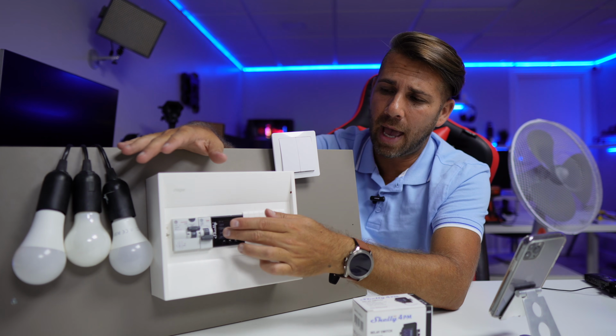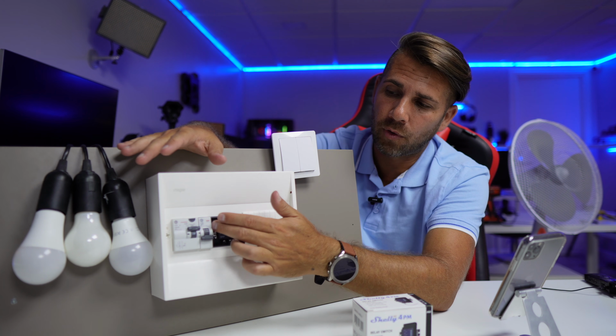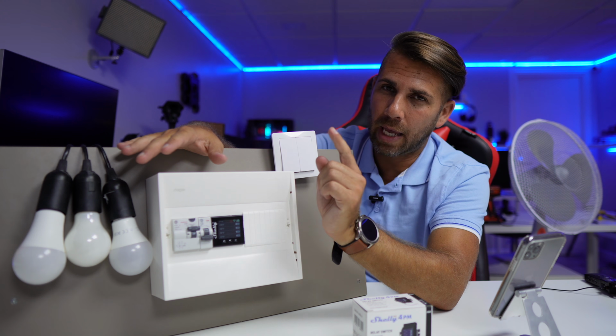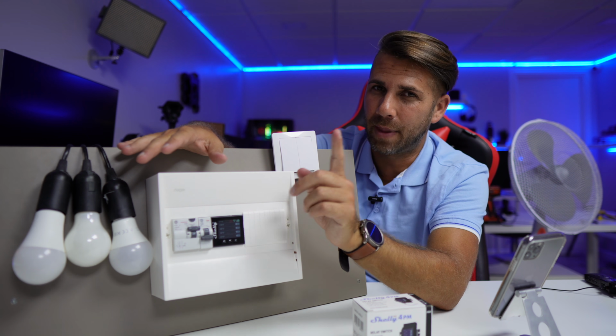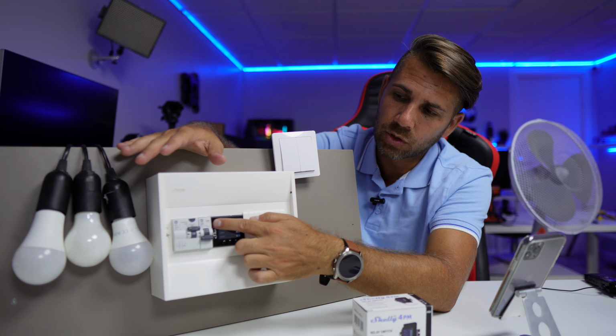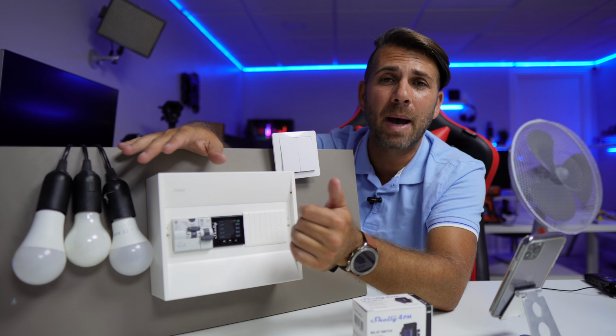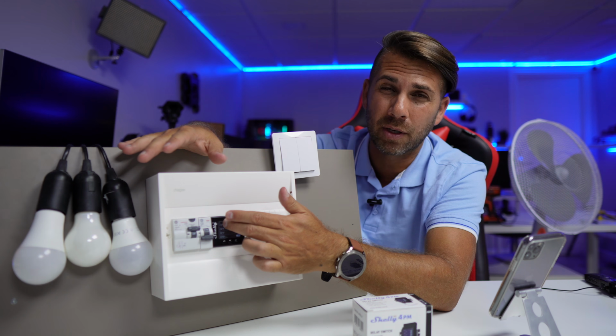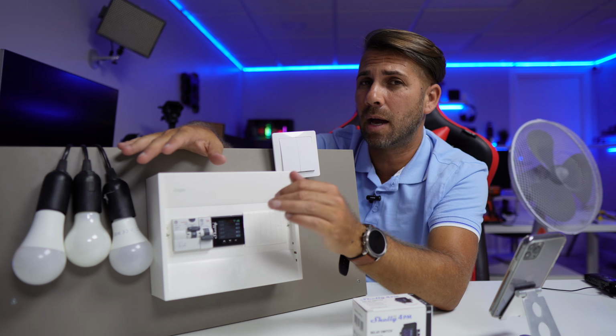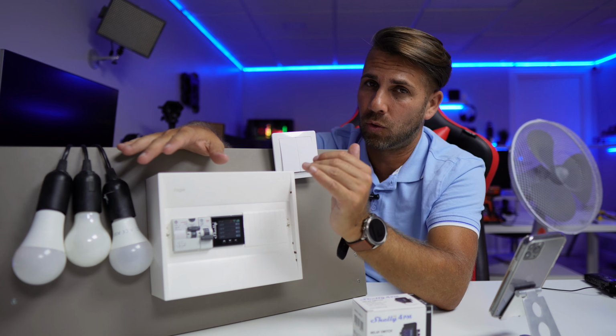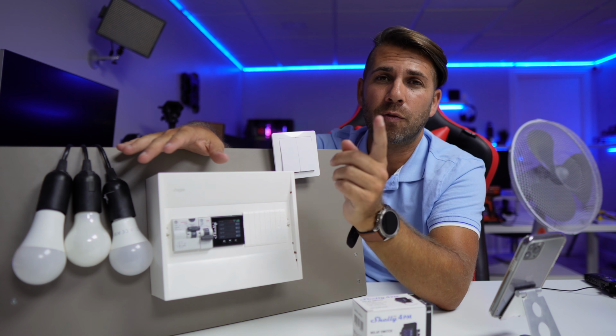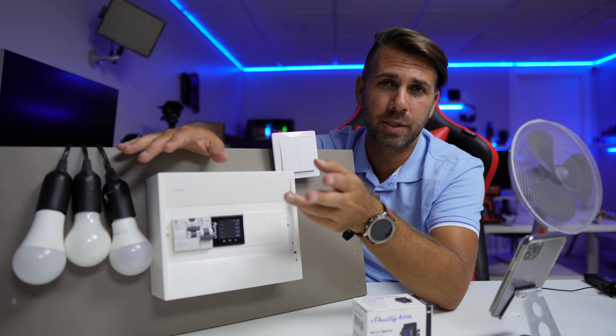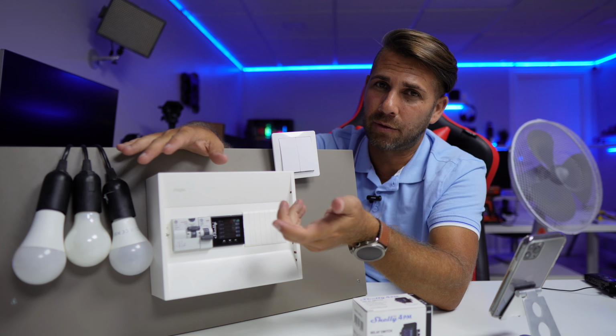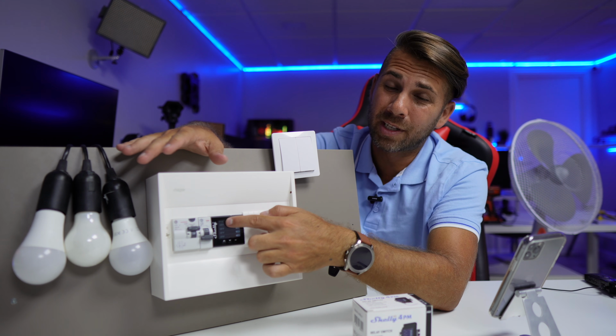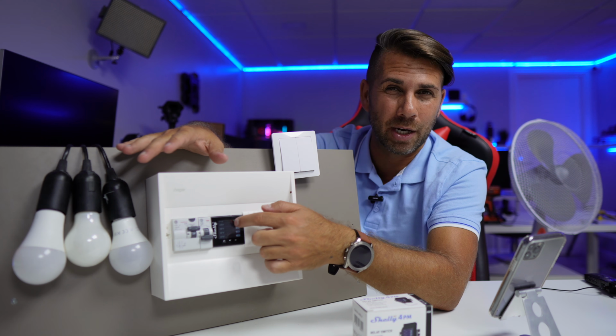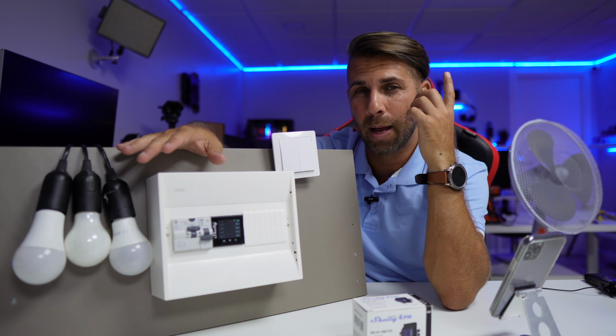We have 16 amps, 3,500 watts for each output, but a maximum of 40 amps overall. If I'm using 2 devices and each one is using the maximum capacity, 3,500 plus 3,500, that means I'm already at 7,000 watts of a maximum of 8,800, which is 40 amps. So I need to be careful because I'll only have 1,800 left for the other 2 channels. This is something we should plan ahead for.